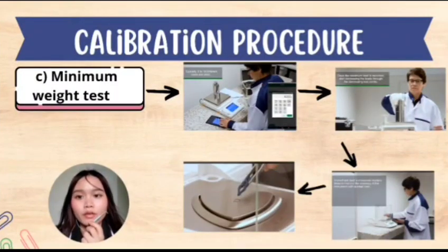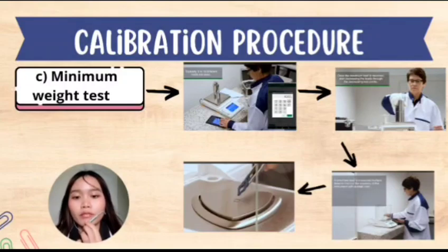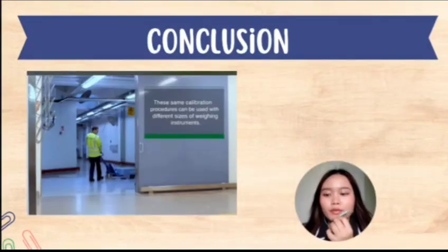The last procedure is the minimum weighing test. This is required within some industries like the pharmaceutical industry. The purpose of the minimum weight test is to find the smallest load that can be measured while still achieving reliable results. In this procedure, a small test load is measured multiple times to find out the accuracy of the instrument with a small load, for example, a clip. This same calibration procedure can be used with different sizes of weighing instrument.